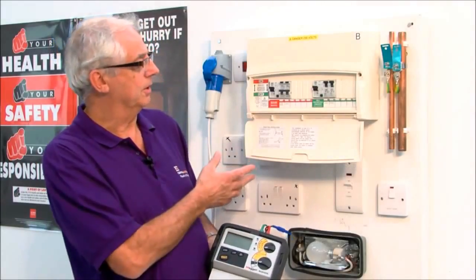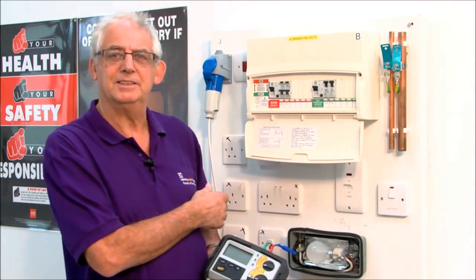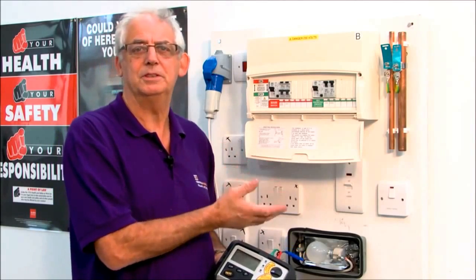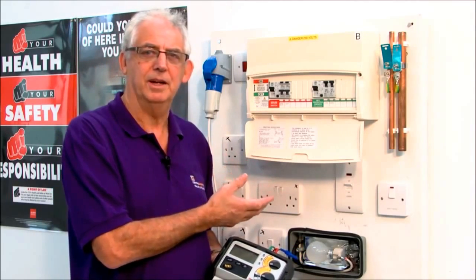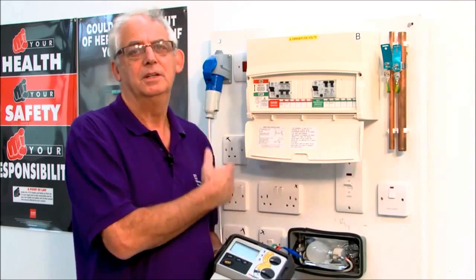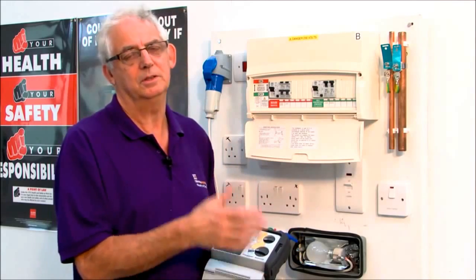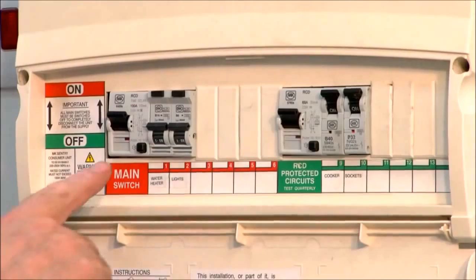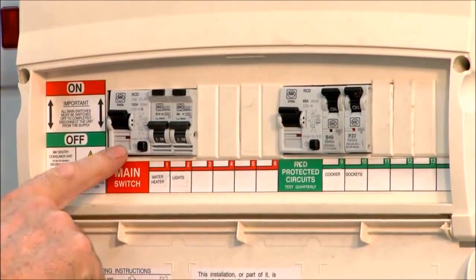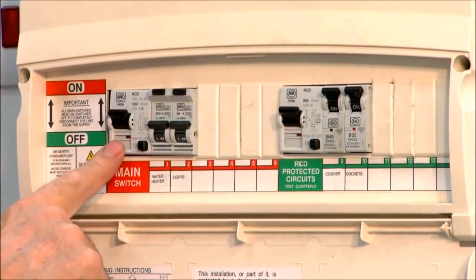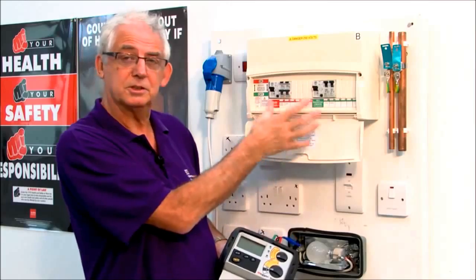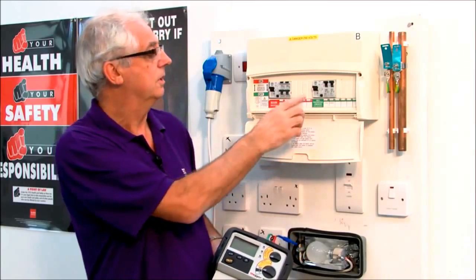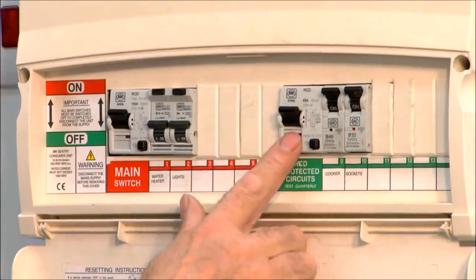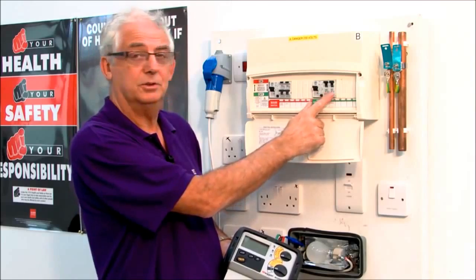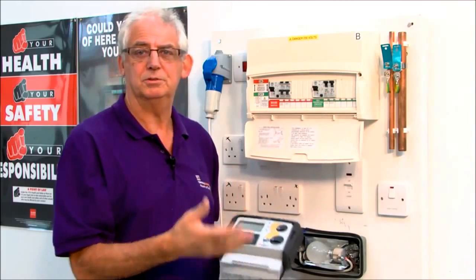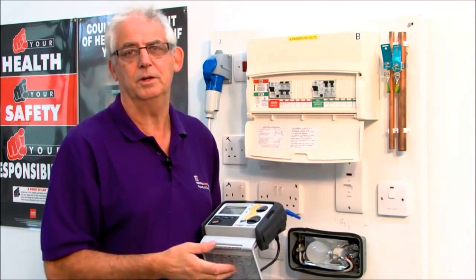This is a test rig that we use to simulate a TT system. As we know, with a TT system, you would have to have an RCD as a main switch and RCDs throughout the board. Now, sometimes you can use RCBOs for every circuit if you want to, or maybe you want just a split board because of cost, so you've got half of the board with another RCD and 2 circuit breakers. The choice is really yours. You can do it whichever way you like.